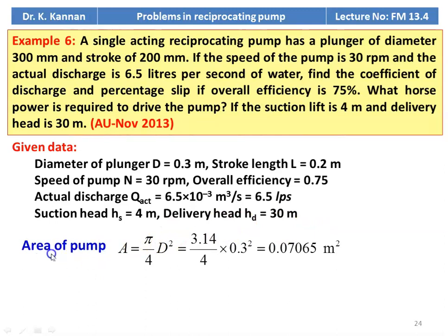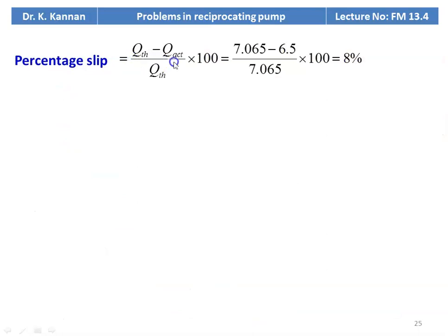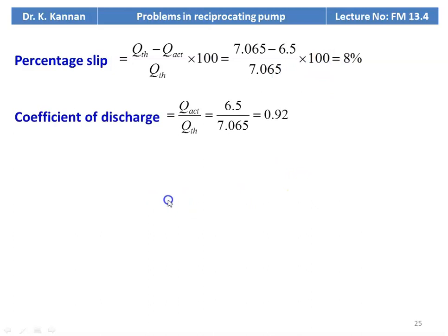The area of the plunger A = π/4 × D² = 3.14/4 × 0.3² = 0.07065 meter square. The theoretical discharge Q_theoretical = A × L × N/60 = 0.07065 × 0.2 × 30/60 = 7.065 × 10⁻³ meter cube per second or 7.065 liters per second. The percentage of slip = (Q_theoretical − Q_actual) / Q_theoretical × 100 = (7.065 − 6.5) / 7.065 × 100 = 8%. Coefficient of discharge = Q_actual / Q_theoretical = 6.5 / 7.065 = 0.92.